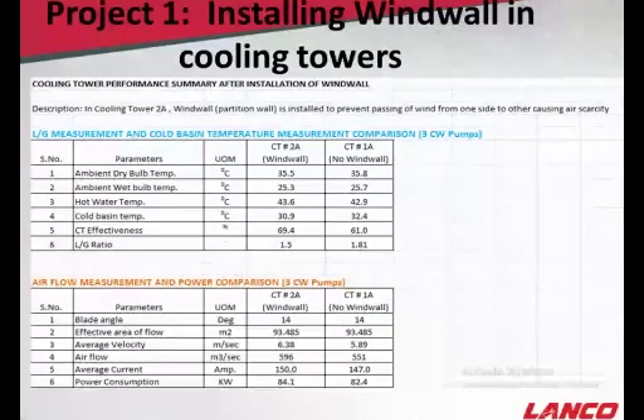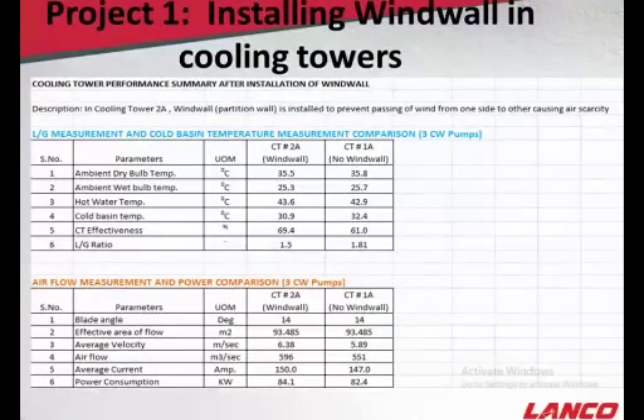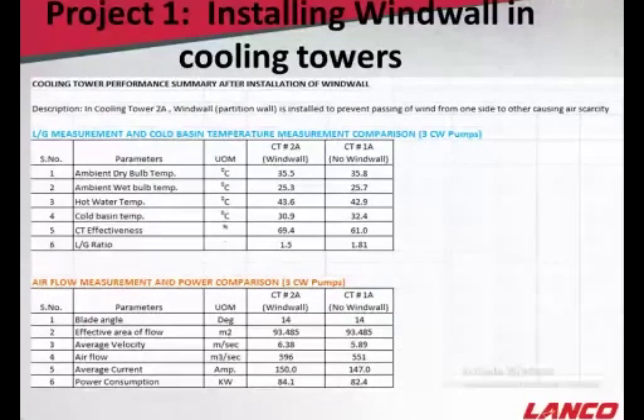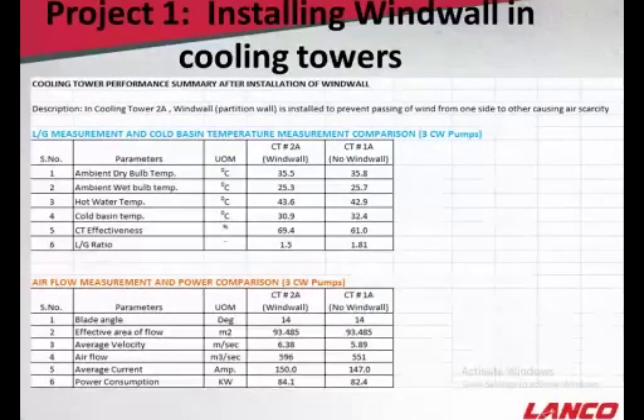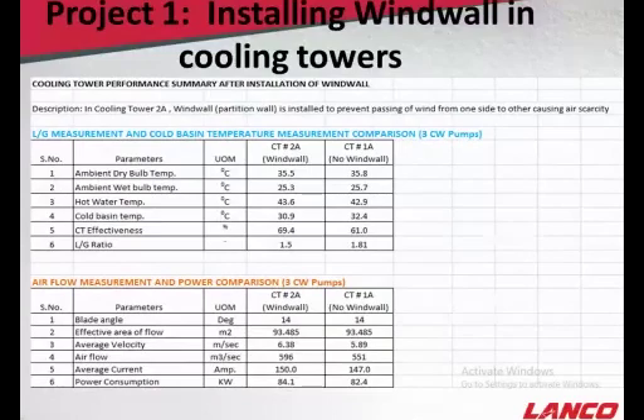But we utilized this margin by increasing the blade angles to keep the current same, but the airflow to the maximum. Earlier, in the different seasons, we were changing the blade angles. In the winter, we need to minimize the angle to minimize the airflow, and in the summer we need to increase the angle to increase the flow, so as to get the advantage. But after doing this, we have monitored the airflow as well as the maximum angle, and the maximum loading on the fan, that is amperes on the fan, was within the design range. And the ultimate effect on the CT basin temperature that was going to the CW inlet was encouraging. So this was improved.